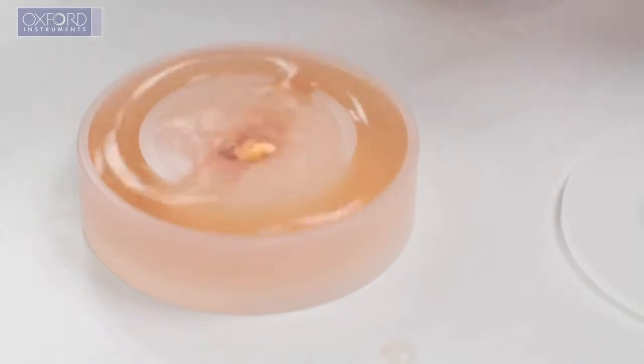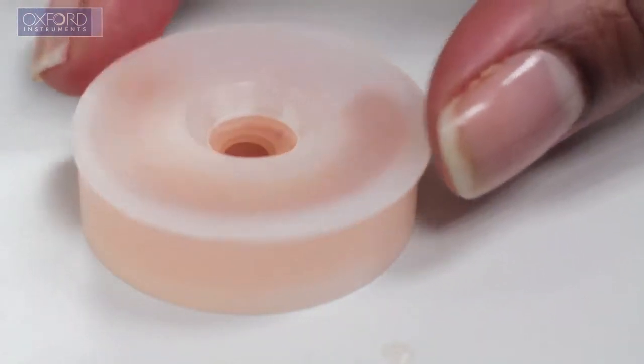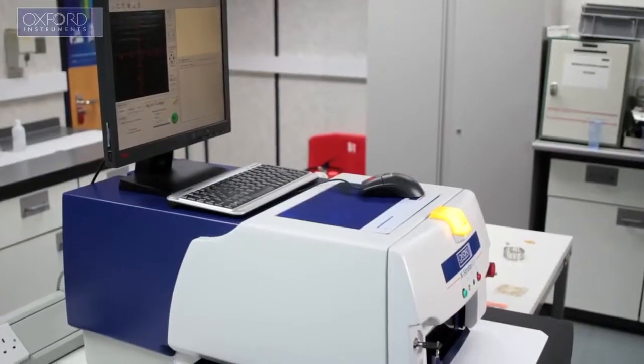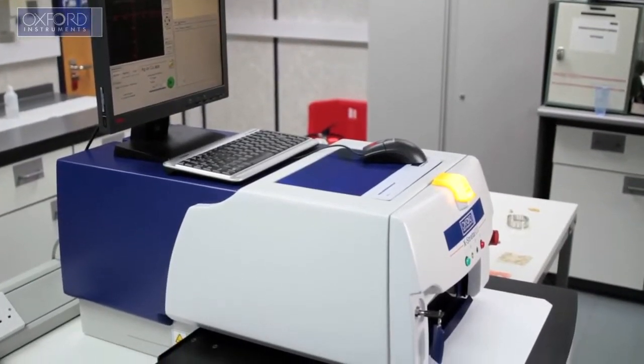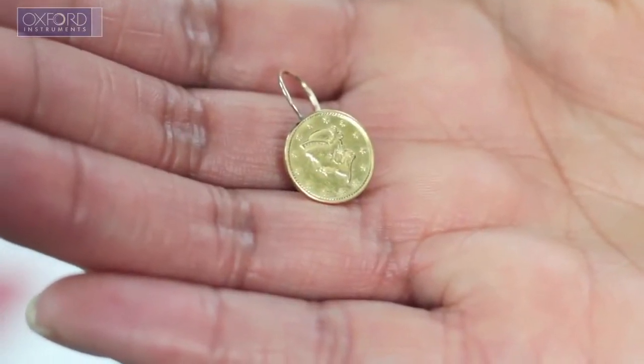And for solution analysis, the sample is simply poured directly into the Oxford Instruments cup and analyzed. When measuring samples for elemental composition, the analysis steps are the same. For example, the X Strata 920 can determine the precious metal concentration of jewelry pieces.